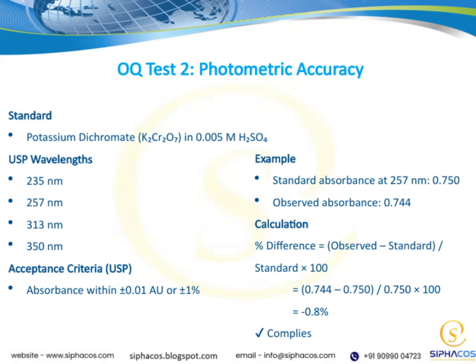Let's take a look at this example. The standard absorbance at 257 nanometers is 0.75, and the observed absorbance we measured is 0.744. To see how close these values are, we perform a simple calculation of the percentage difference. We subtract the standard from the observed, which gives us minus 0.006, then divide that by the standard value of 0.75 and multiply by 100 to get the percentage. This results in approximately minus 0.8%. Since this is within the acceptable range, it indicates that our measurement complies with the quality standards.